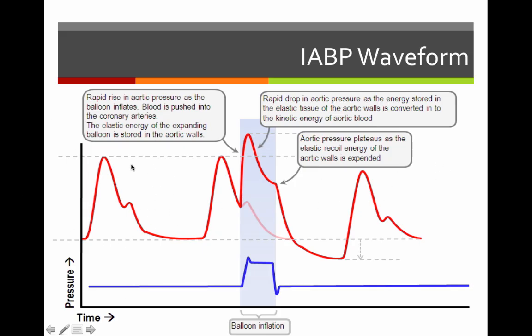So here we have an unassisted beat, and your balloon pump can be programmed to inflate with every beat, every other beat, every third beat, and so on, depending on what the cardiologist wants. Here it looks like it's inflating with every other beat. So here we have an unassisted beat before any of it kicks in.